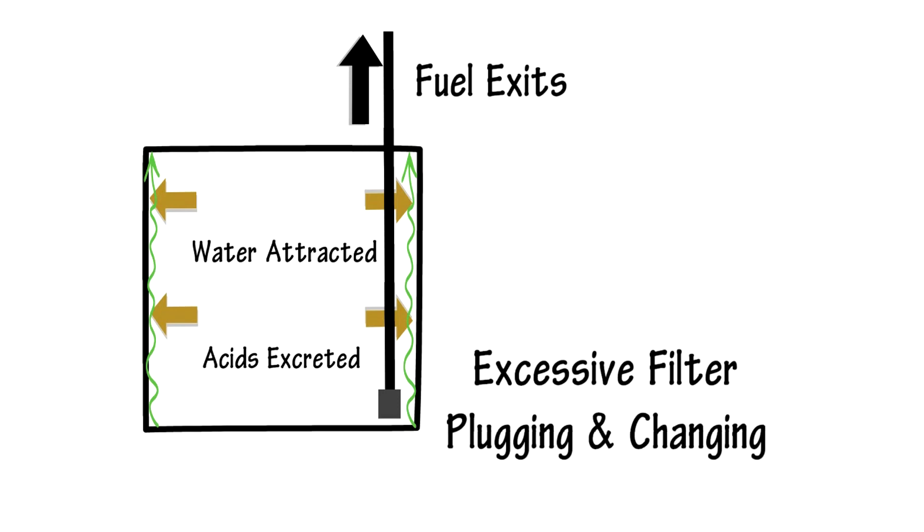Excessive filter plugging and changing is a sure sign of a problem like microbial growth in the fuel tank.